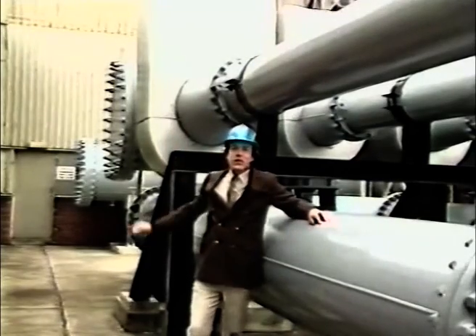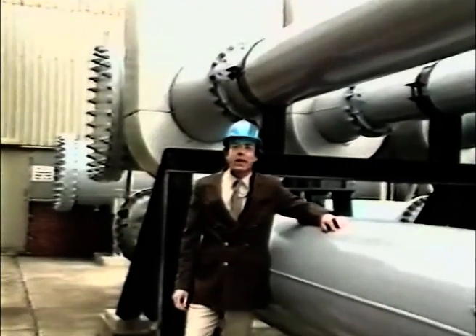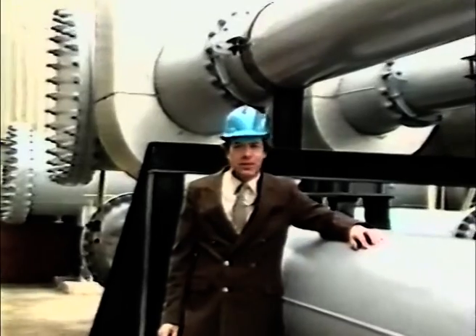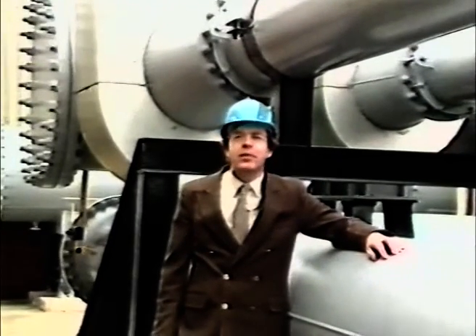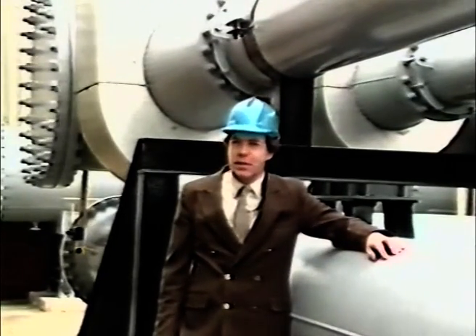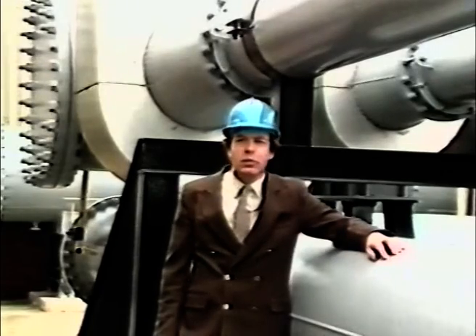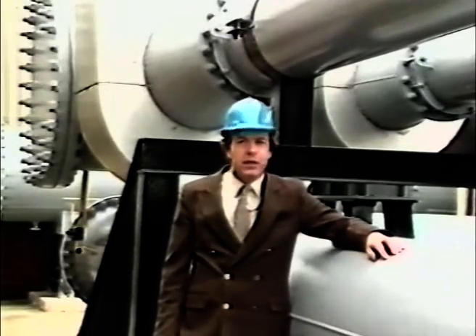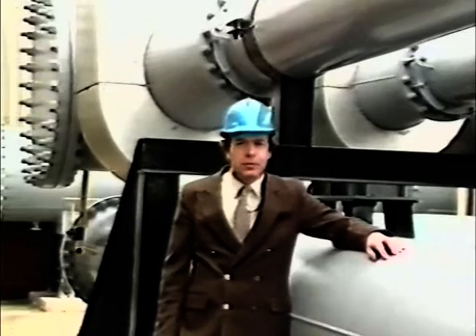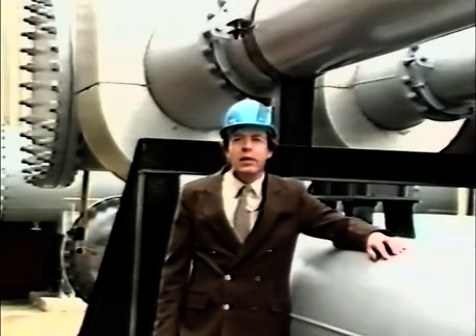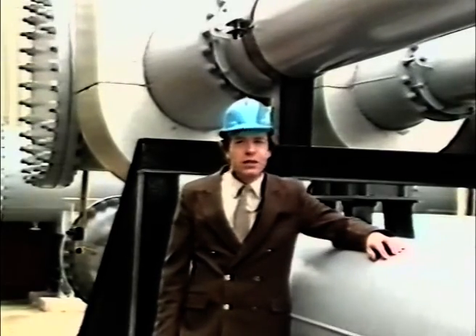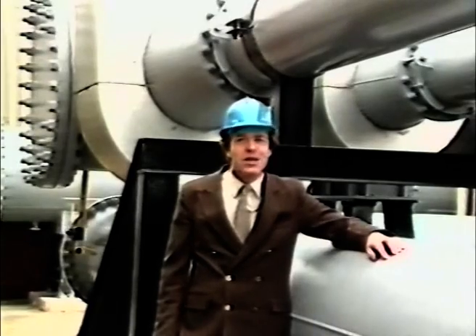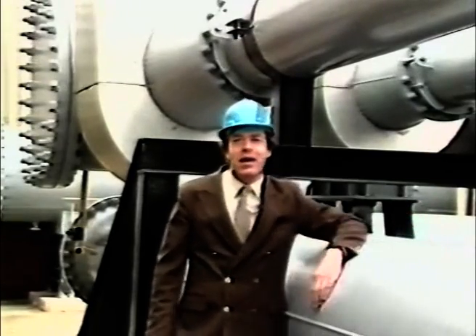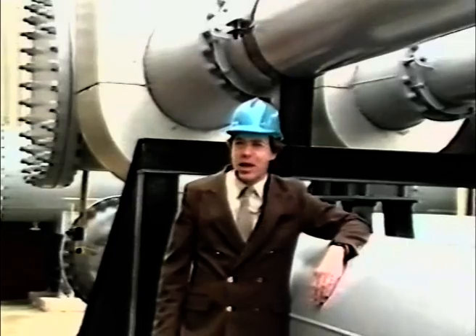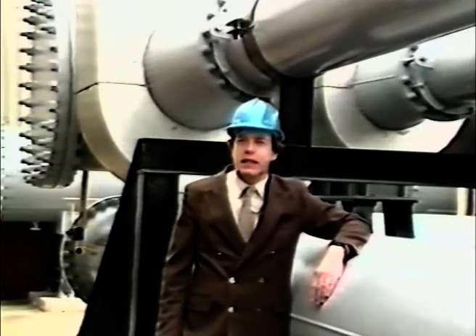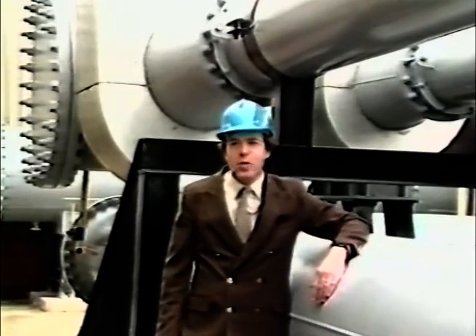Beneath this building is a swimming pool-sized reservoir containing 1,000 cubic meters of water. Not a conventional reservoir, but with a shape specifically designed to eliminate aeration, which could create unwanted inaccuracies. Because, believe it or not, the immensely powerful pumps which drive this plant can recirculate the entire 1,000 cubic meters in only 6 minutes, which means that these pipes can carry over 10,000 cubic meters per hour. That's almost 3 tons of water every second. Follow me.